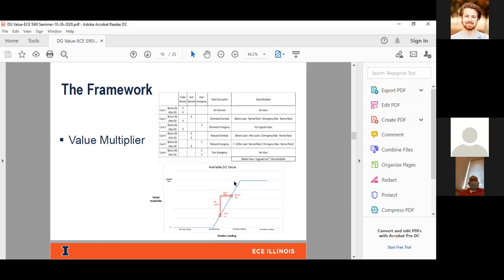Utilities see problems and start initiating projects and want to put in an upgrade anytime you're over the normal operating limit and you're reaching the emergency limit. That's when utilities start funding projects, and that's where DG can really provide value in terms of, can you defer that funding or help reduce that funding overall. So the font here might be a little bit small, but case 1 is looking at an asset where before DG and after DG, you're still under the normal operating limit. So there's really no value there. There's no overload, and you won't see any value for a DG that's downstream of this asset.